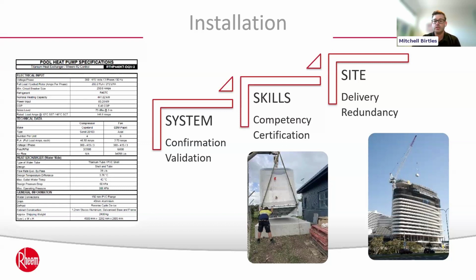Part of site location incorporates design and clearances for airflow, which are vital for heat pump operation. We tend to look at this factor quite a bit in the design phase as the manufacturer. If the unit is going to be enclosed, has the plant room been louvered, and has that been cleared by the manufacturer as acceptable?